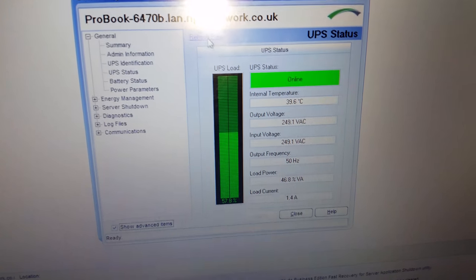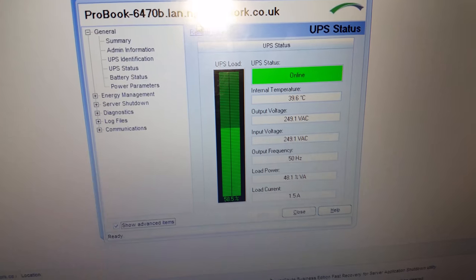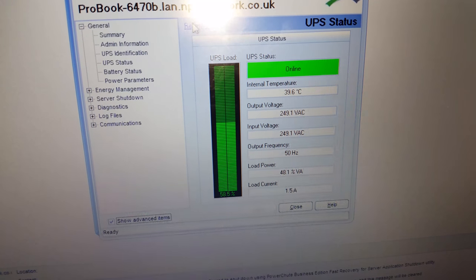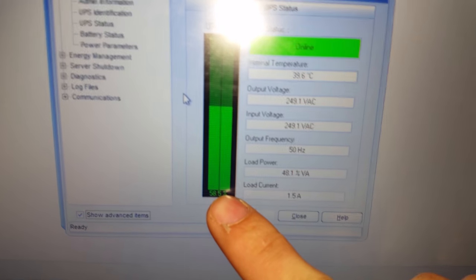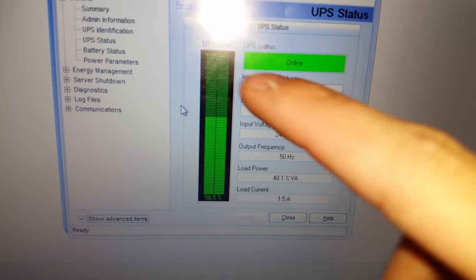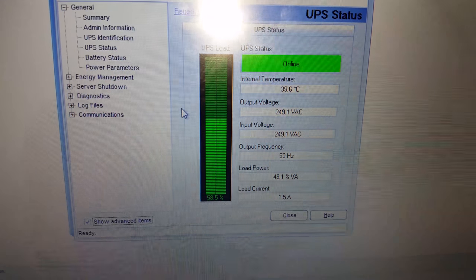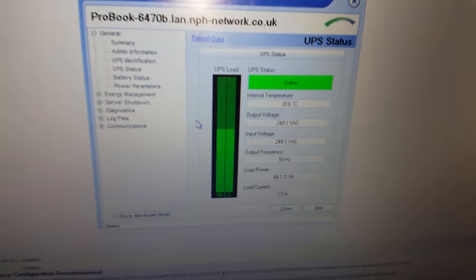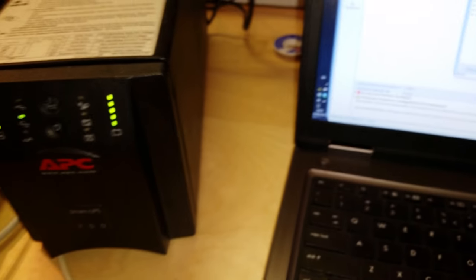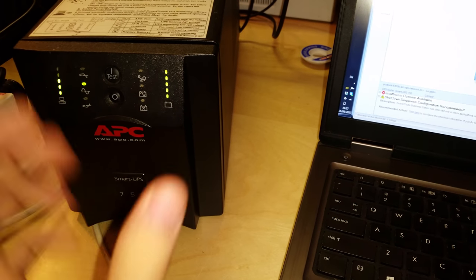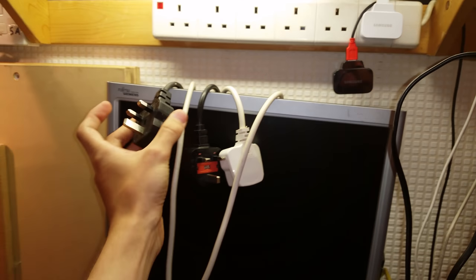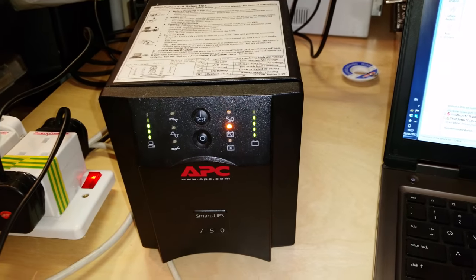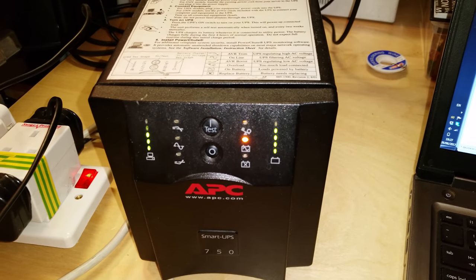And that loads it up to over halfway with all those on. So if I refresh the load, you can see here the load is 58.5 percent. That's 1.5 amps. Now I think this is roughly where it'll run, about 55 to 65 percent load. This is what I'm going to calibrate it to, but I'm going to bear in mind these are the old batteries still. The way you calibrate these is you basically when it's like this, you just unplug it from the mains. So if I go like this with the load on, it's now running on battery and we let it run until it's completely dead.